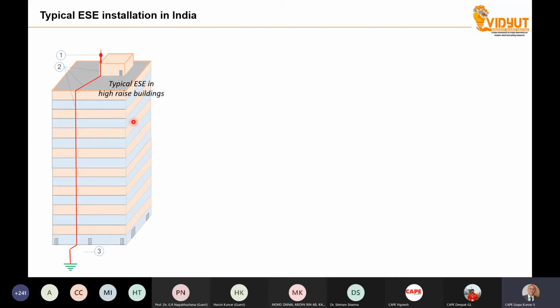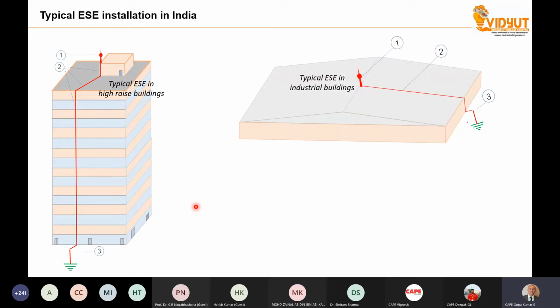Imagine a high-rise building. At the top of the building, there is an attractive rod. Even from a little bit far away, you will be able to see the rod. There is an attractive rod, then there is a down conductor, normally a 70 square millimeter copper flexible insulated conductor.